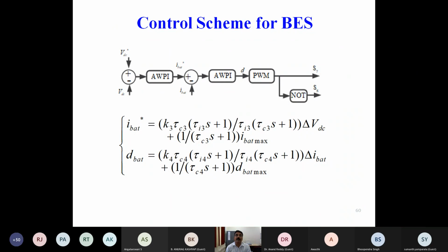So that is also very important, this anti-wind-up system. The same system can be used for battery energy storage. Here also, if you are having larger errors, anti-wind-up is very much required. And we have to see what the requirement of the battery is, what the state of charge is, because if the battery is full, we cannot charge it, since overcharging will lead to loss of the battery and it may get damaged. So it is very important to have coordination in the control for battery charging as well.